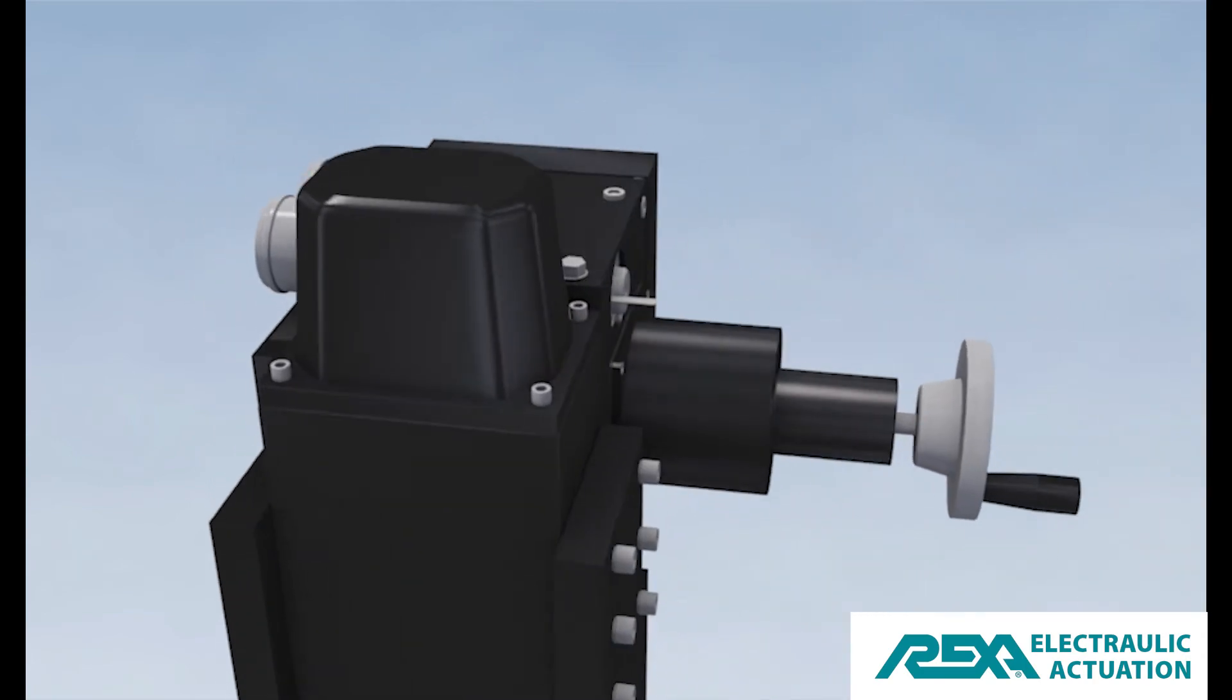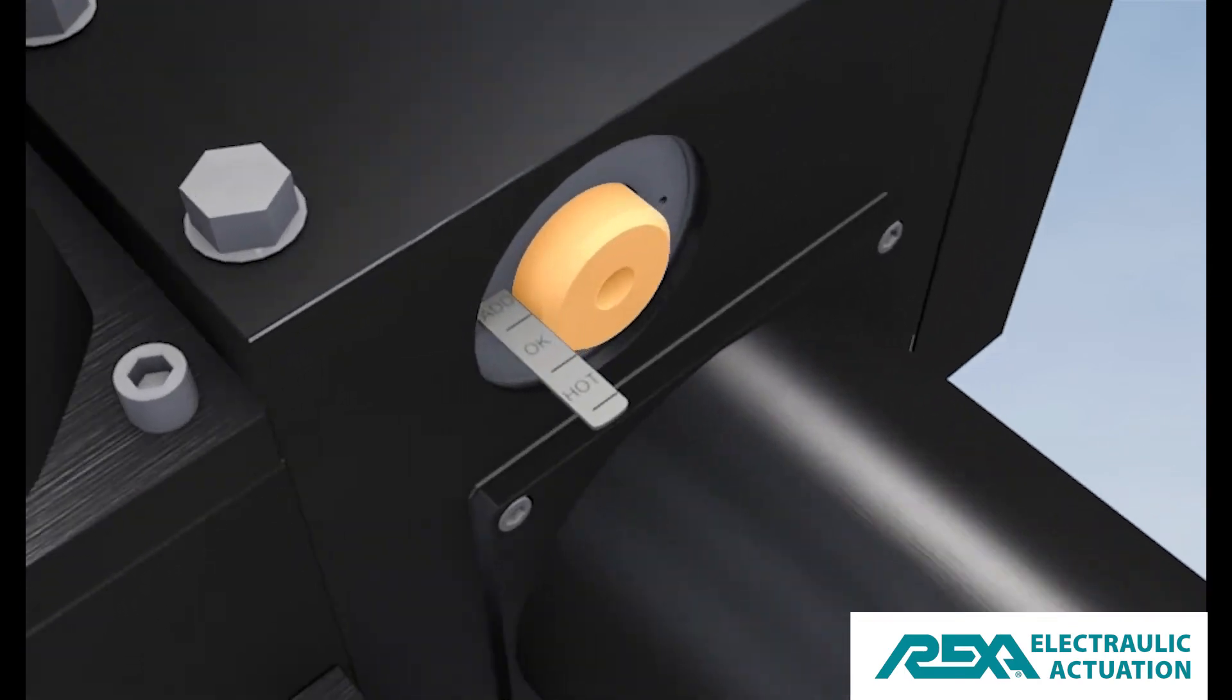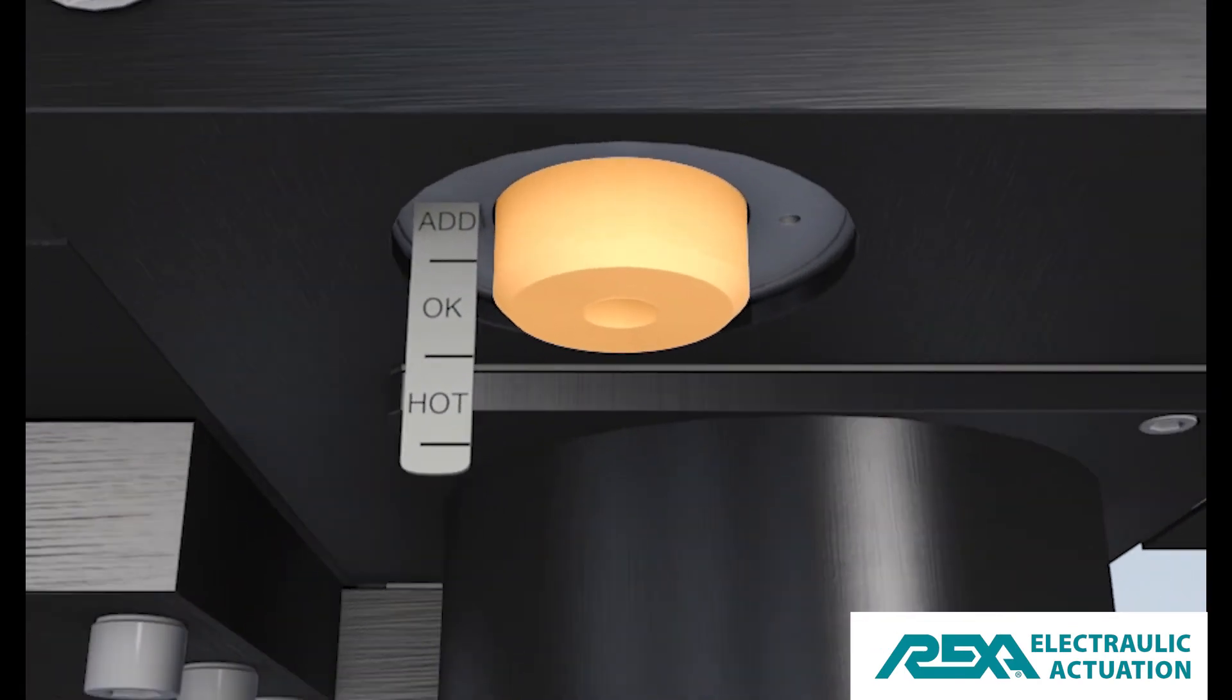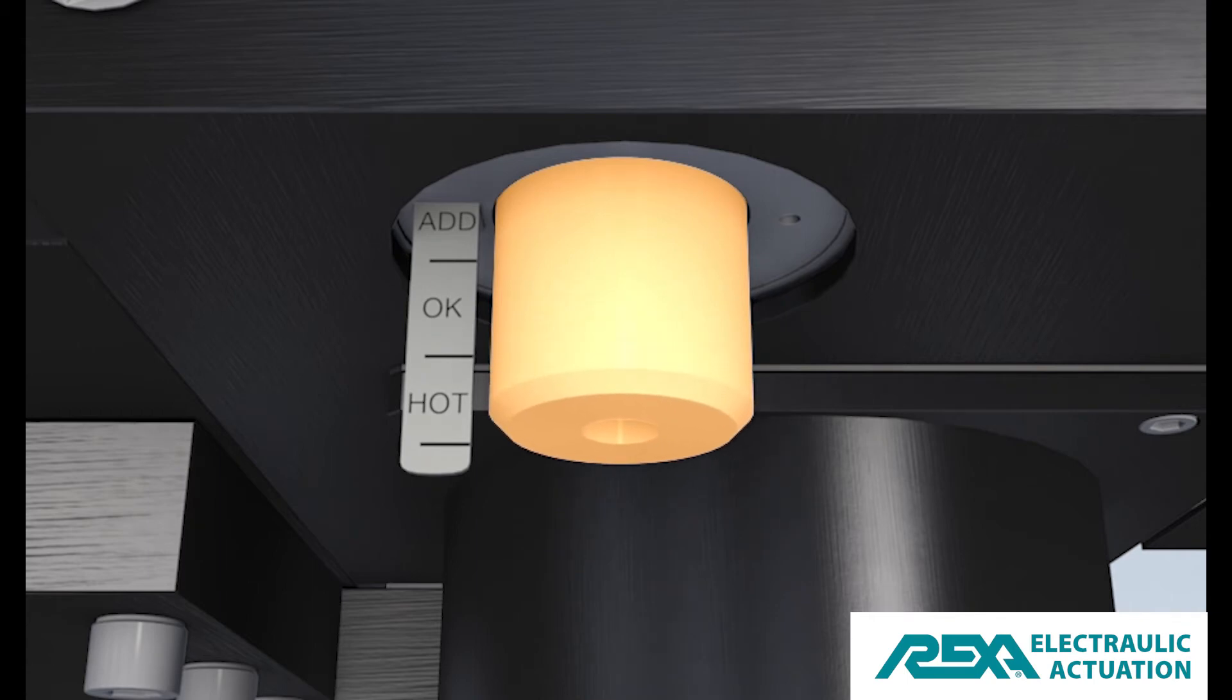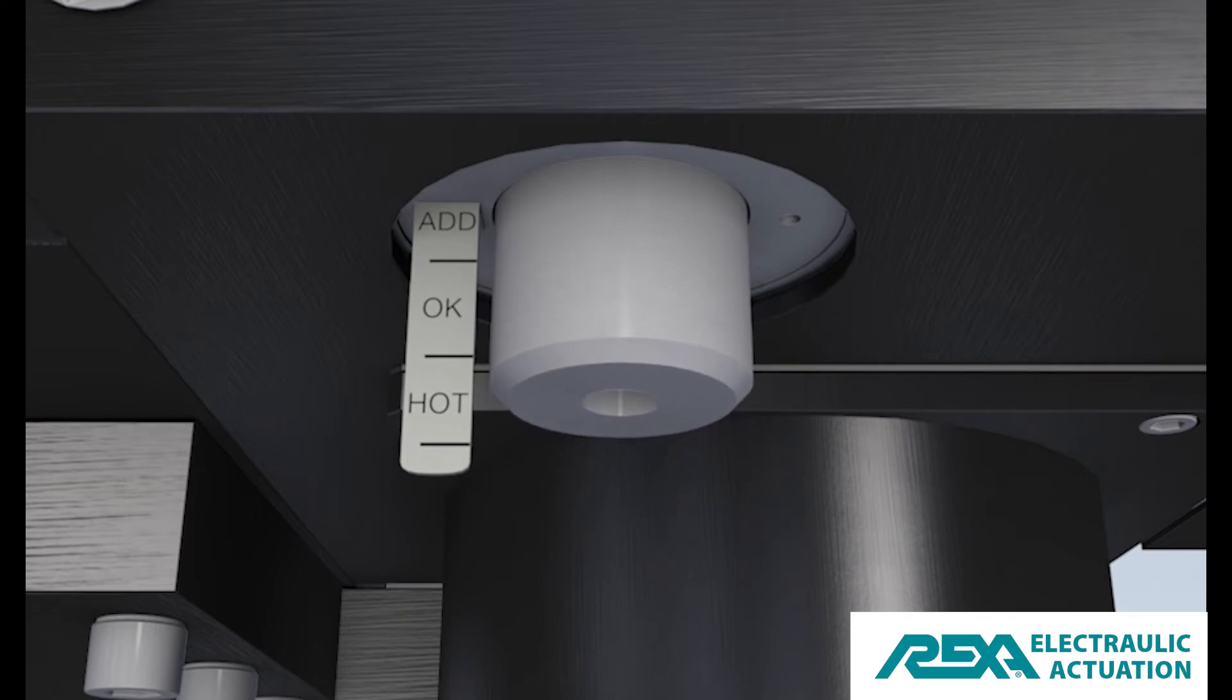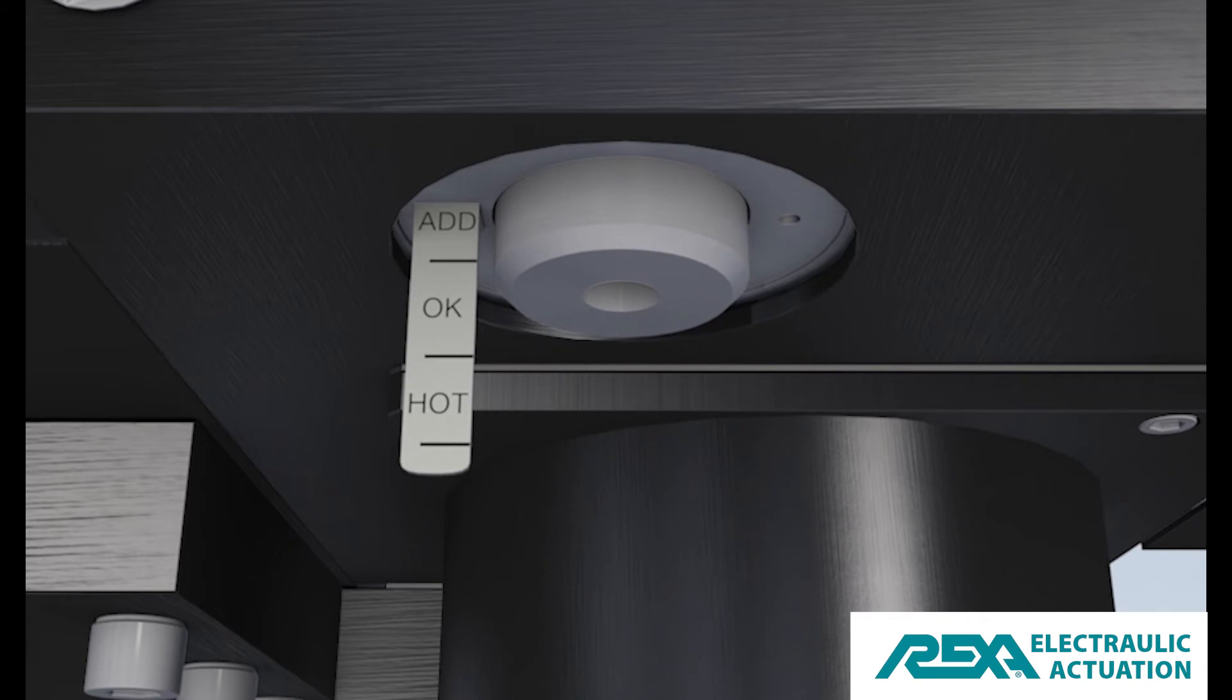The REXA actuator contains a thermal expansion chamber that provides an auxiliary volume for expansion and contraction of oil as it heats or cools depending on plant environment and operating conditions. The spring-loaded oil level indicator moves in and out along a level scale to identify the system oil level.